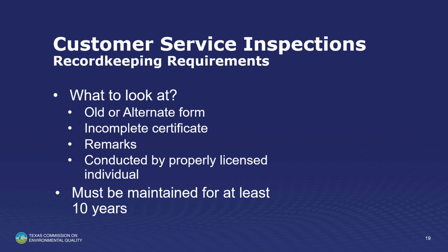Incomplete certificate, remarks. Every time I do a CSI, I promise you there's remarks on there. I'll put on there I did a lead test or I didn't do a lead test. Why didn't I do a lead test? Because it had PEX, it had PVC. It didn't have any solder joints or brass connections. It's just because I didn't have to.